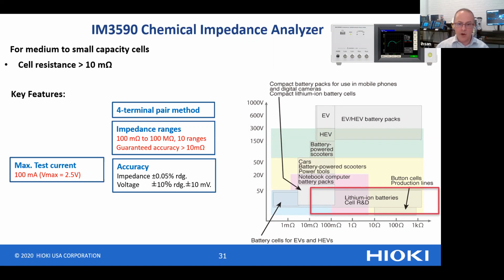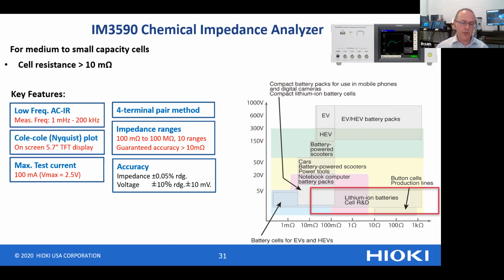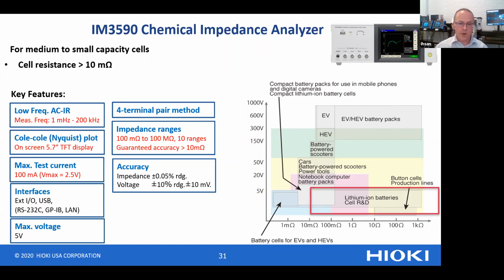Obviously the megaohm range isn't necessary for batteries, but it is an LCR meter or an impedance analyzer, so it has a broader range of applications, especially for research and R&D. It's also capable of the low frequency ACIR method that we mentioned, where it's able to sweep from 1 millihertz all the way up to 200 kilohertz. And it can display the Cole-Cole or Nyquist plot on its built-in display. Again, it's fully compatible with most production needs, as it has the full range of interfaces. And since it's intended for individual cells, the maximum voltage is 5 volts.